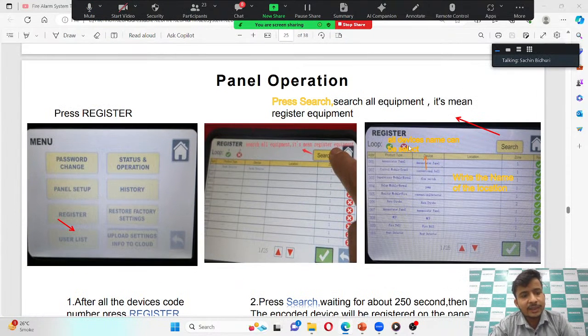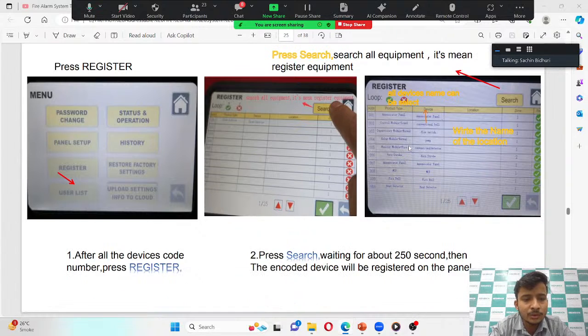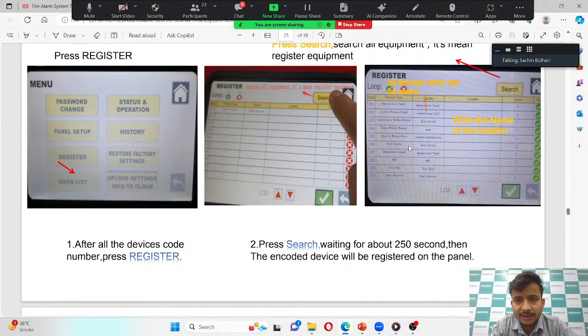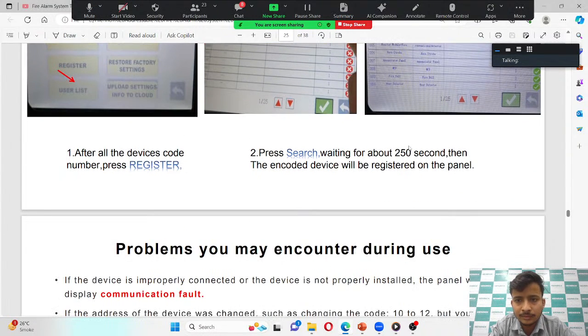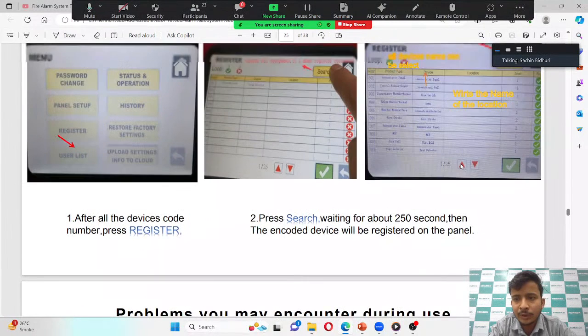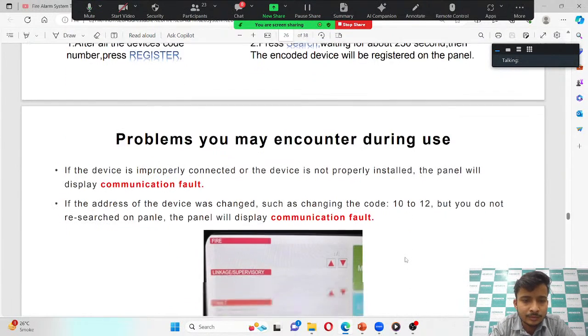For registering the devices in the panel, once you give the address to all the devices, you need to go to register. Then you press the search button. After pressing the search button, the panel will take up to 250 seconds, and after that time the panel will automatically show all the devices in the same register as per their address code and product type. You just need to press the save button, and all the devices will be saved, or registered, in the panel.